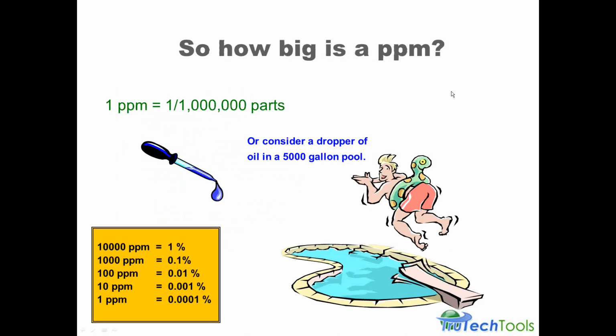When we measure CO, we measure using a unit of measure called a part per million, or a ppm. 1 part per million, by definition, is 1 in 1 million parts. So it's a very small quantity. That's what's being measured as a concentration in the gas that's moving through the combustion analyzer. In a more physical sense, you can think about a 5,000-gallon hot tub or small pool and 1 dropper of oil. That is about 1 part per million on a volume basis.